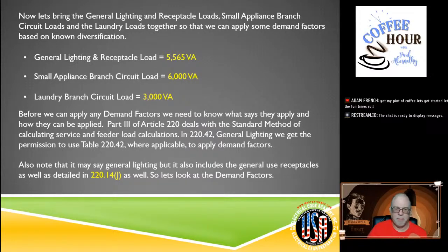All right. Now, before we can apply a demand factor, we need to know what it says about applying and how they're applied. So if you look at part 3 of Article 220, it deals with the standard method. Of course, that's what we're doing today. On another coffee talk in the future, I will do the optional method. But right now, the reason I'm doing the standard, and I know most people will say, Paul, I don't use the standard method. I always use the optional method.